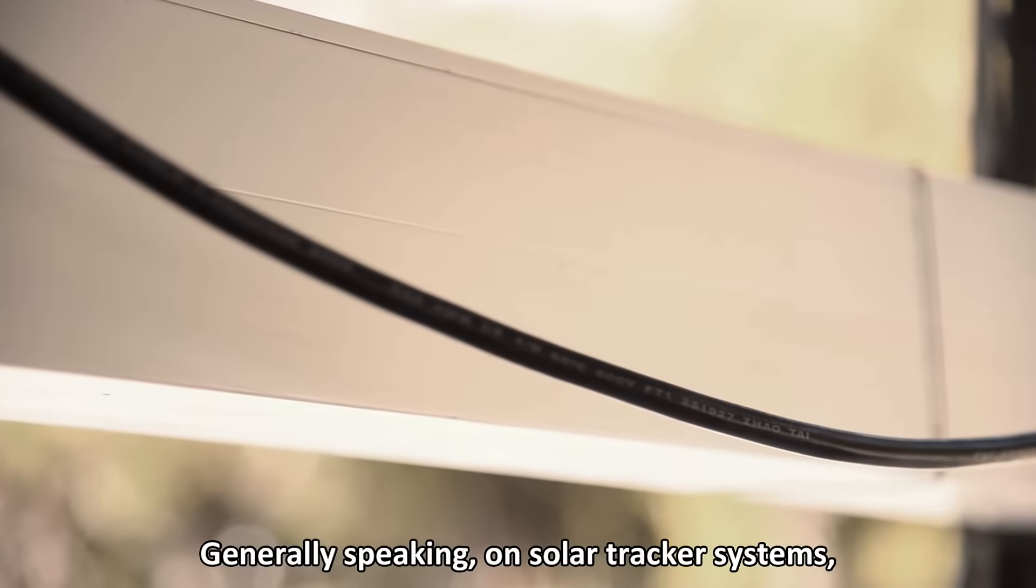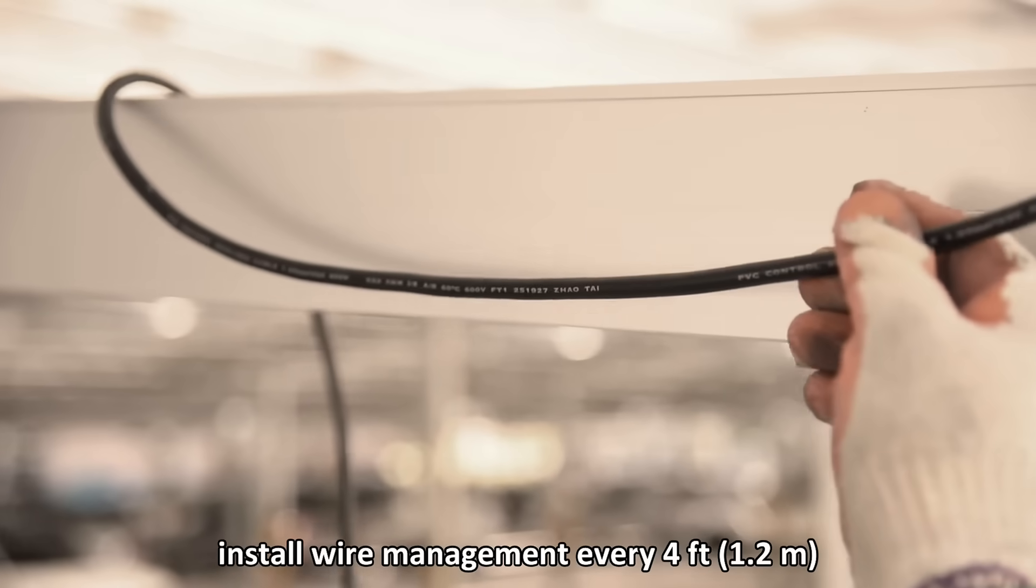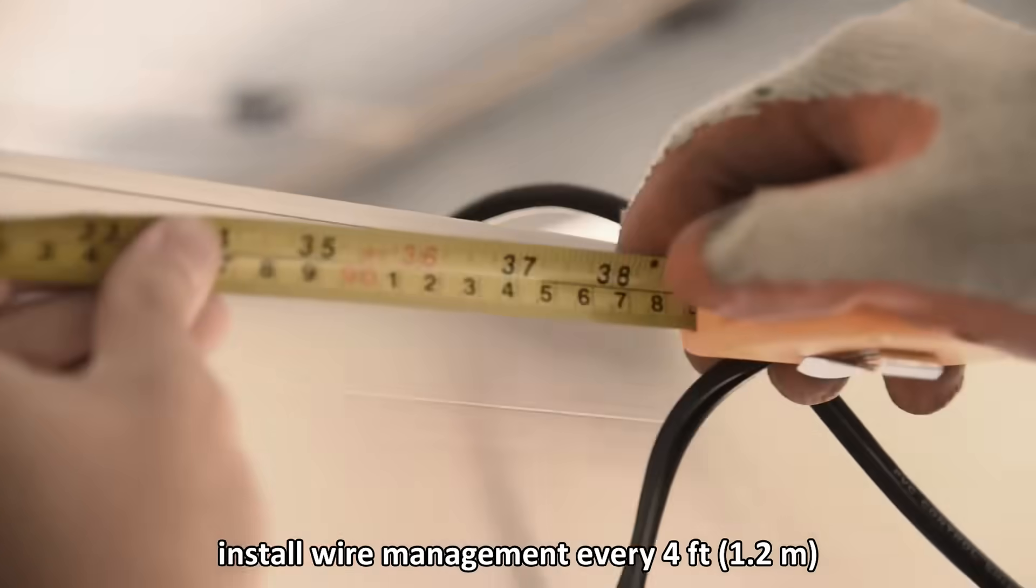Generally speaking, on solar tracker systems, install wire management every 4 feet or less along the torque tube or secured to the module frame.